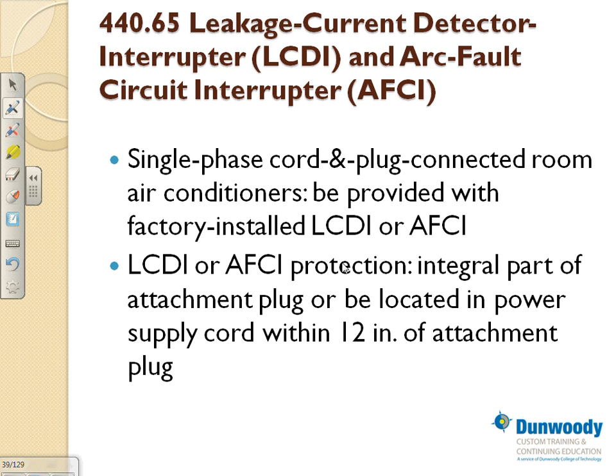Leakage detector and arc fault circuit interrupter in this equipment: only single phase, only plug-in connected equipment. You have to provide either leakage or arc fault circuit interrupter protection on them. You can have them as part of the attachment plug or in the power supply cord within 12 in. of the attachment plug. Right now, if you use this in residential, guys, you are plugging it into a GFCI and arc fault circuit interrupter anyway, especially if it's 120 volt, all the 120 volt, 20 amp and 15 amp have to be arc fault circuit interrupter protected in residential. So earth leakage or arc fault circuit interrupter protection in this equipment.